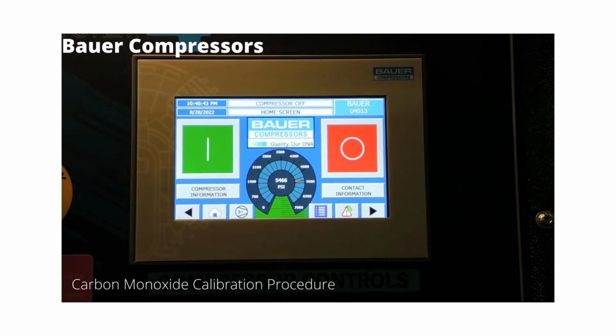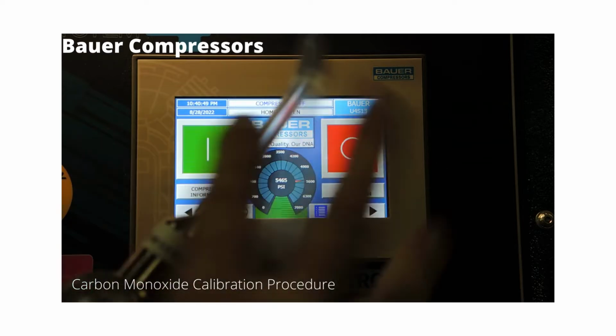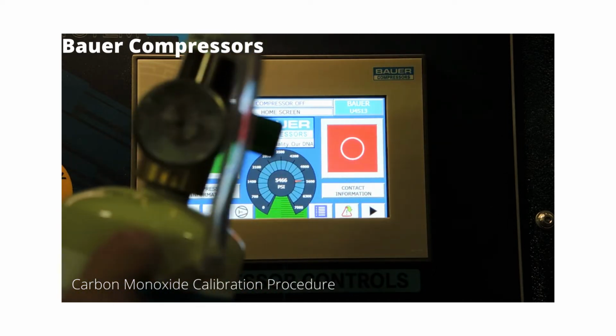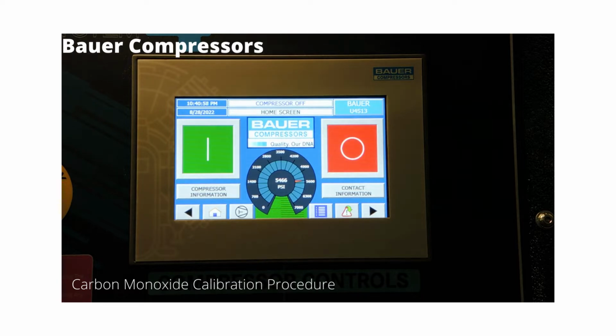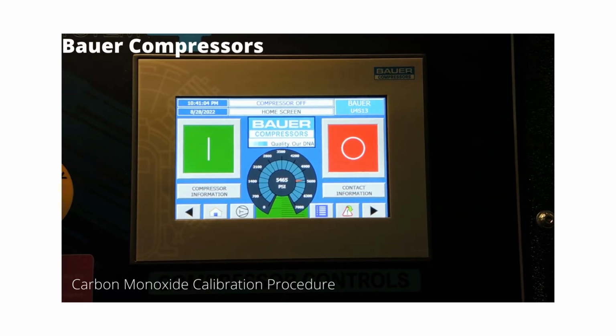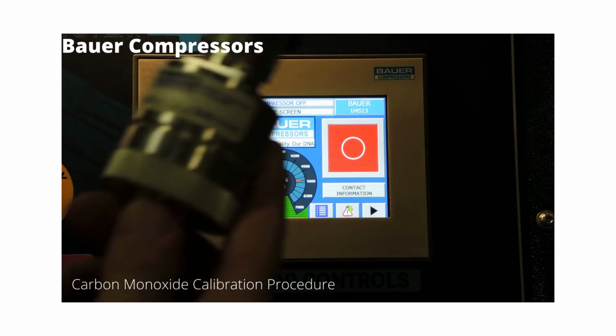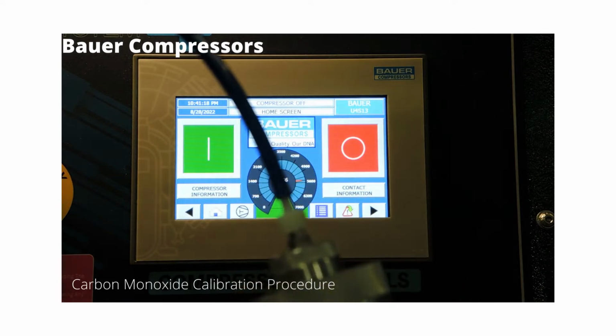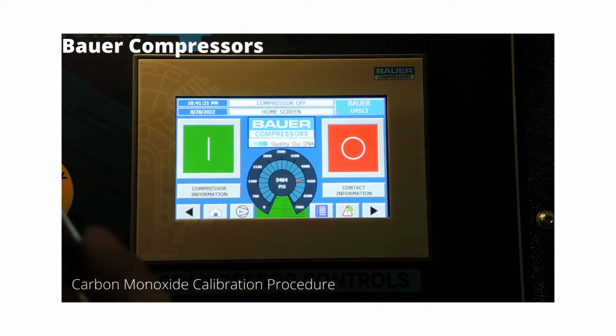Another thing that I like to do is connect the regulator to each of the test gases, and then with the regulator closed, I look at the dial to make sure that I've got pressure on each cylinder. I don't want to start the calibration without cylinders with gases in them. Also, you're going to want to familiarize yourself with the compressor system and find the CO sensor. This is the CO sensor, a sensor 134. It's usually going to have a blue hose connected to it. You're going to want to find where that's at on the compressor before you do the calibration.